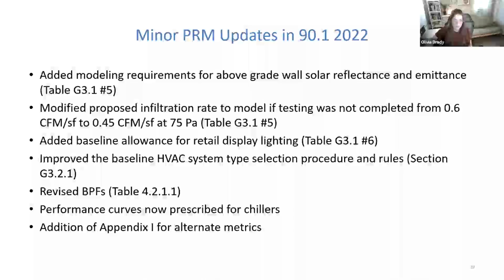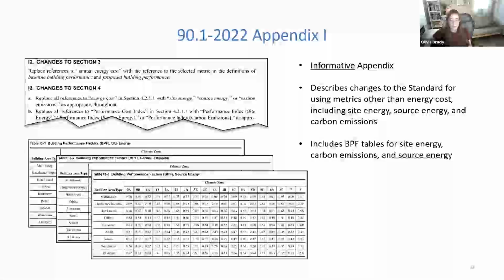All right, so there are some minor PRM updates in 90.1-2022. Modeling requirements were added for above grade wall solar reflectance and emittance. The proposed infiltration rate to model if testing was not completed was reduced from 0.6 to 0.45, and a baseline allowance was added for retail display lighting. The baseline HVAC system type selection procedure and rules were improved quite a bit in 90.1-2022. Of course, there are revised building performance factors to reflect the change in stringency with this new addition. The performance curves are now prescribed for chillers, and there's an addition of Appendix I for alternate metrics. And we'll look at this Appendix I a little bit more.